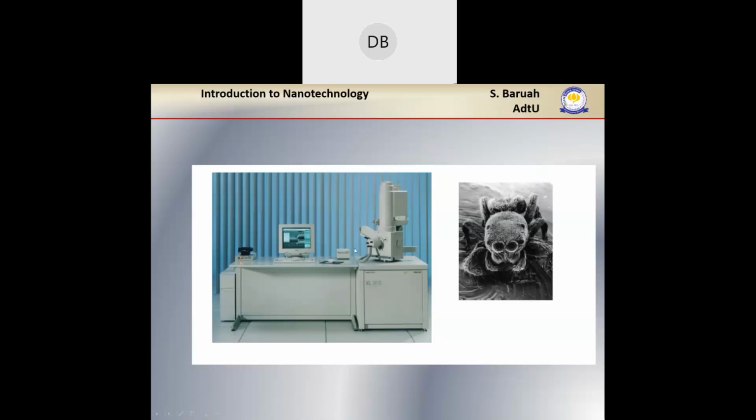In an environmental SEM, we actually divide the column into a number of stages. All right. Basically, inside the column, think of it like stage 1, stage 2, stage 3, stage 4. The first stage will be very, very high vacuum. That means extremely low pressure inside, so that the initial acceleration of the beam, or the converging of the electron beam, happens. And then the next stage, we'll have slightly higher pressure.